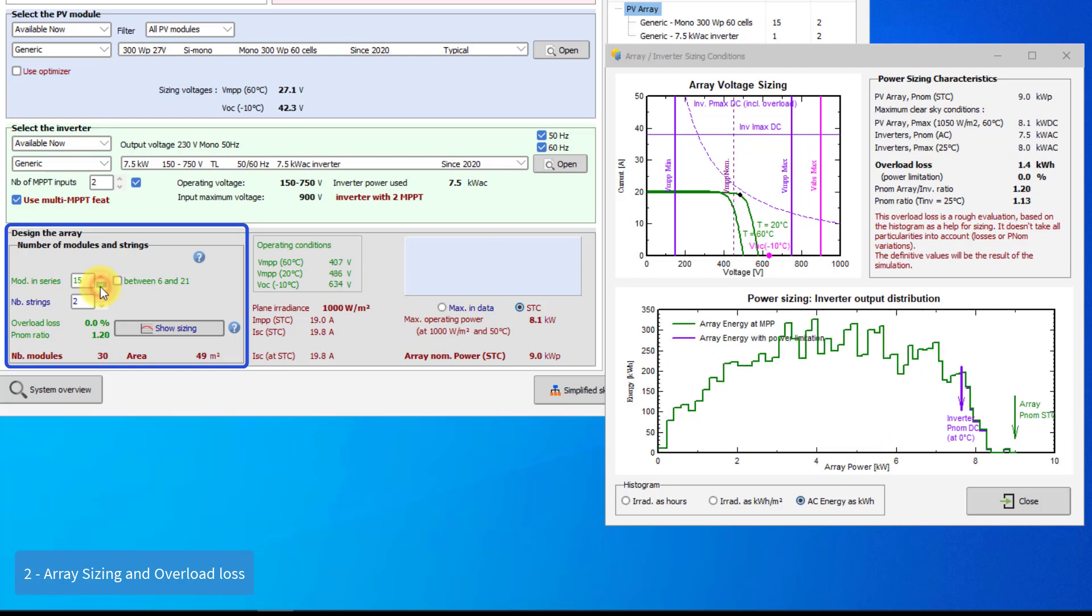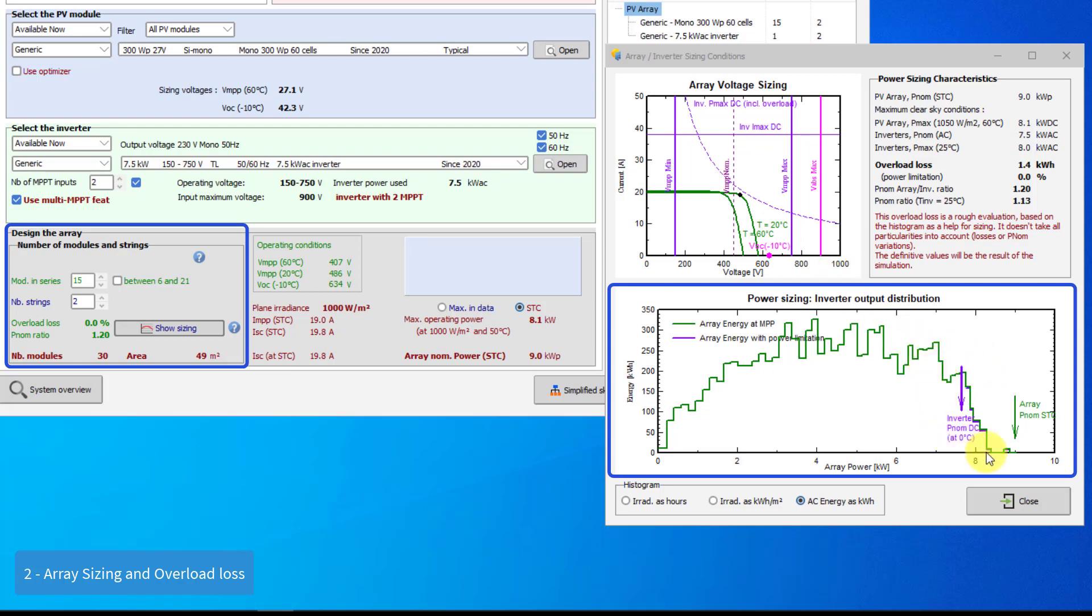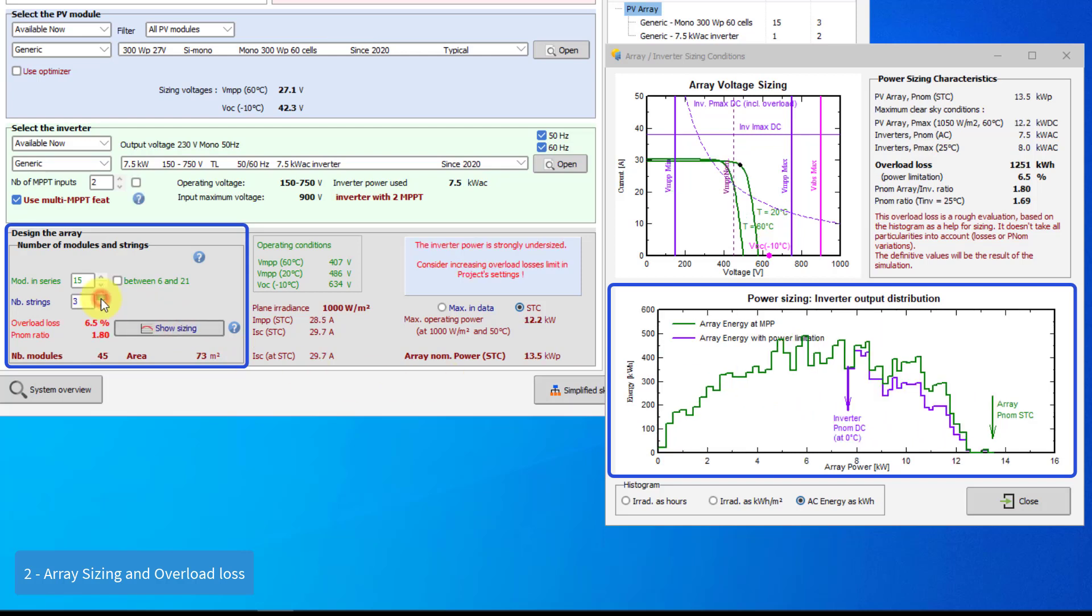We now have to decide the number of strings in parallel according to the array power required. For this, PVSYST shows the distribution of effective power available at the output of the array during the whole year for your meteo data and the plane orientation. Here we have the nominal power at the input of the inverter. The operating conditions above this value will be limited. The violet curve shows you the limited power, and the green curve shows you the available power from the array if the array is working at its maximum power point.